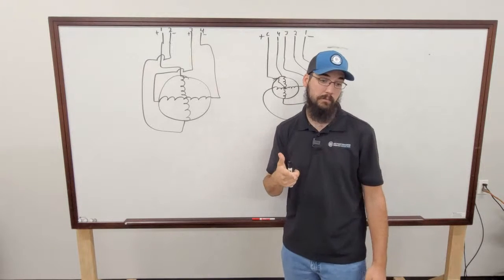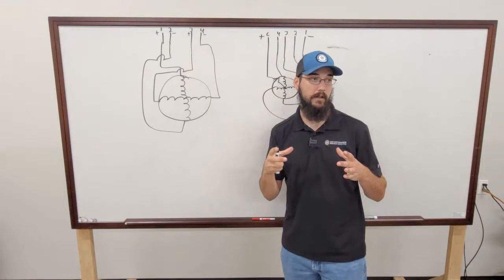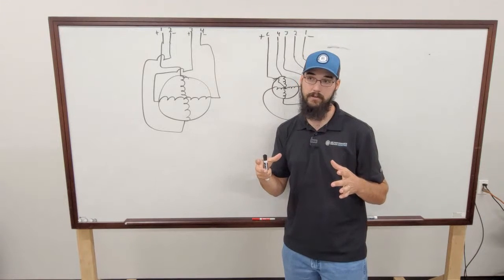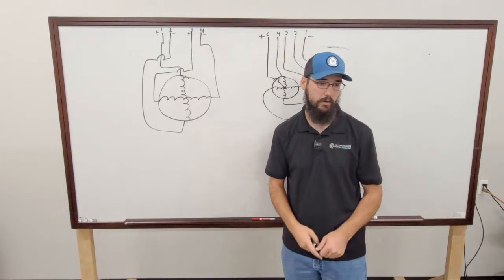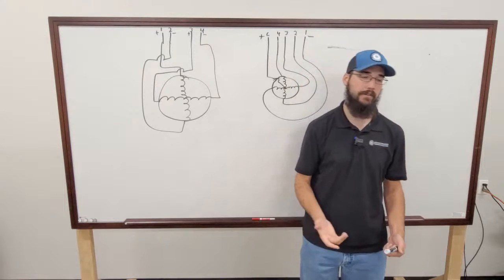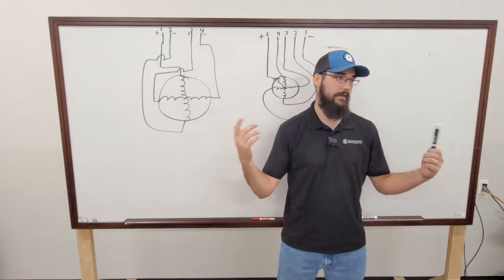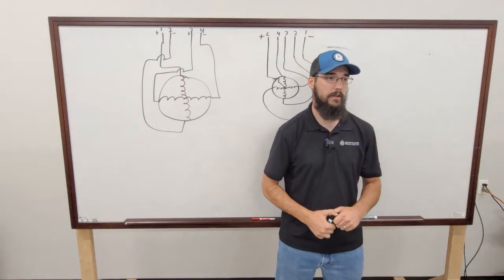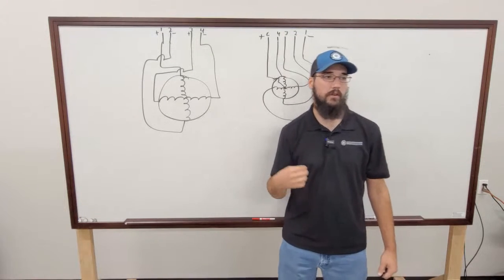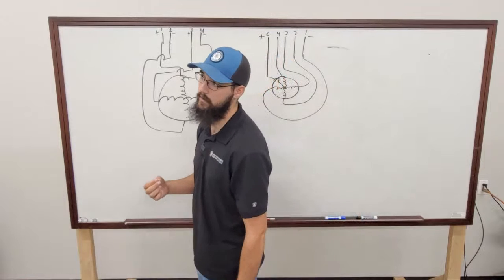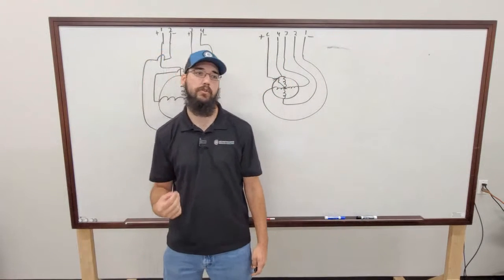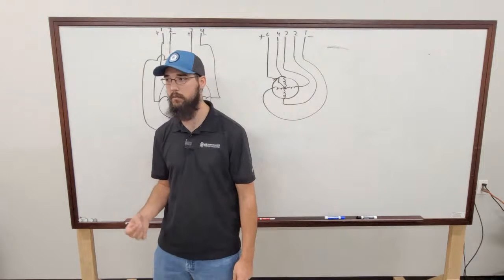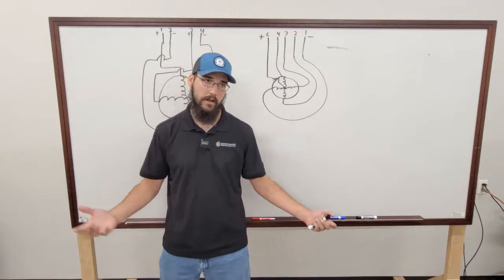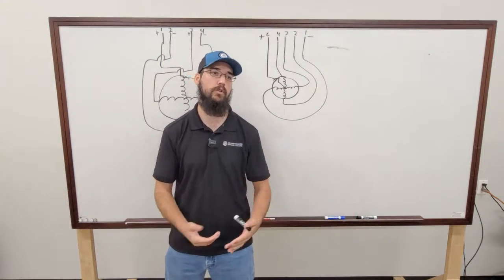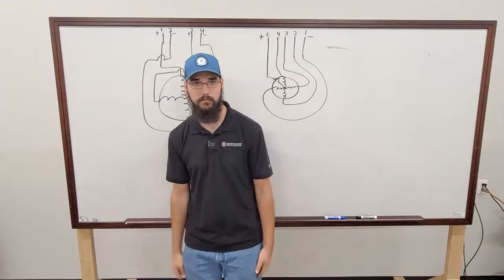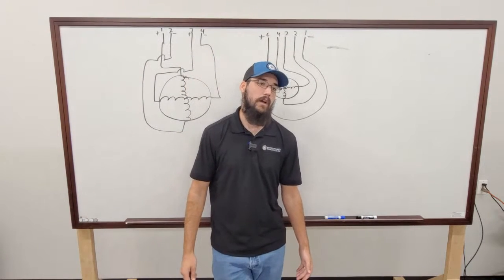Yes, Sporlan does create an EXV tester just for this. We don't have one and never used it, but I do know it exists, so if that's something that would benefit you. One thing nice about most of our modern chiller systems is we can manually control those EXVs in a service test mode. So in our case, we can just use the unit controller as our EXV test driver.